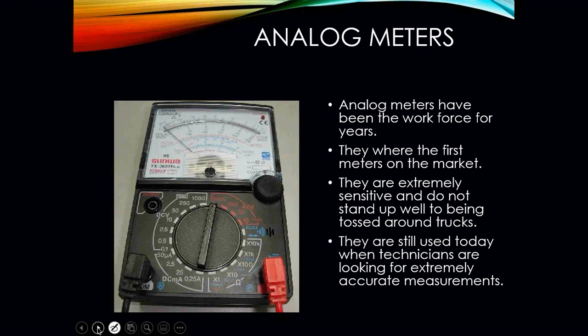And when the technician is definitely looking for accurate measurements, there is equipment out there that needs to be functioning and operating within a certain range of voltage that it's actually rated for, maybe within 5 to 10% of the actual rated voltage. Sometimes a digital meter may not pick that up, so you may have to go to an analog meter to get a very, very accurate measurement of what that particular unit is using.